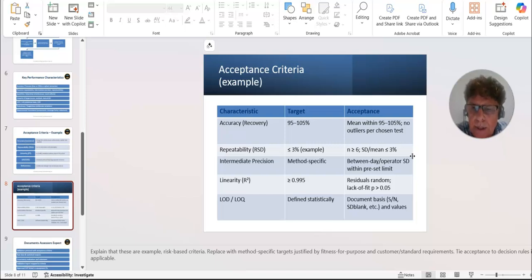We are passing it based on pass fail. Let's say pass was above 10. Well, above 10 plus or minus what? And how did you determine your measurement uncertainty based on your pass fail criteria? You want to define that.